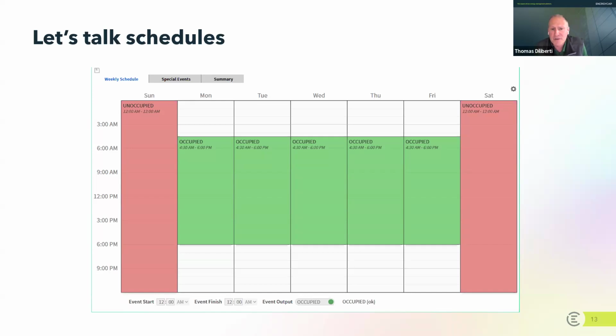The other thing that you have to understand with these schedules is how they prioritize themselves. So how does the system take an occupied schedule and an unoccupied schedule if they are mistakenly put in the same spot? Because as people make mistakes and the system gets confused, somehow the system has to decide what the priorities are. And there's another tab here at the top of the screen.